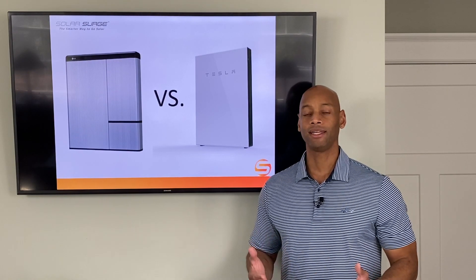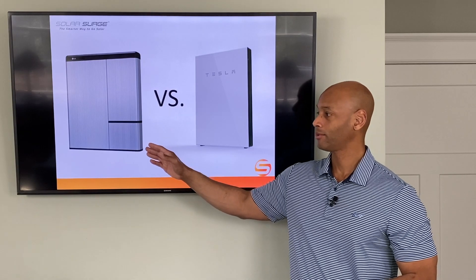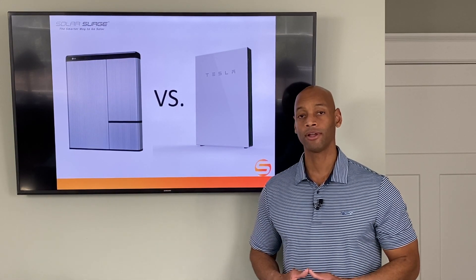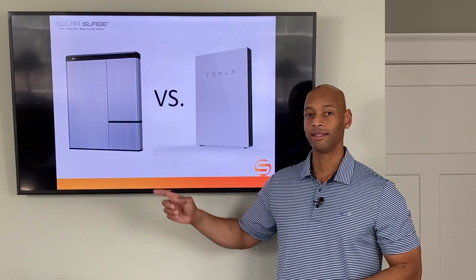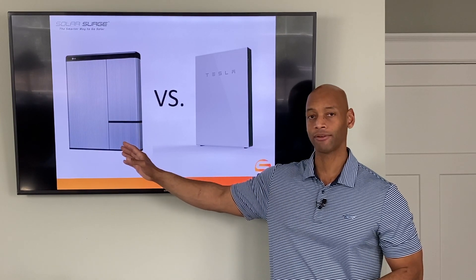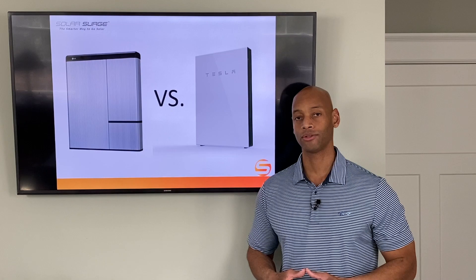When this whole idea of having a lithium-ion battery pack for your house first emerged, LG really made it first to market for nationwide distribution in the U.S. Although it was an exciting capability to offer, there were a lot of bugs in the first generation of the battery — not so much in the physical battery itself, but especially software incompatibilities between the firmware in the battery and the firmware in the inverter it was paired with, such as the SolarEdge storage or the Sunny Boy storage inverter.